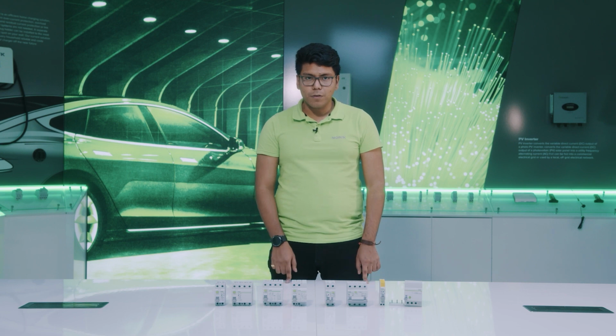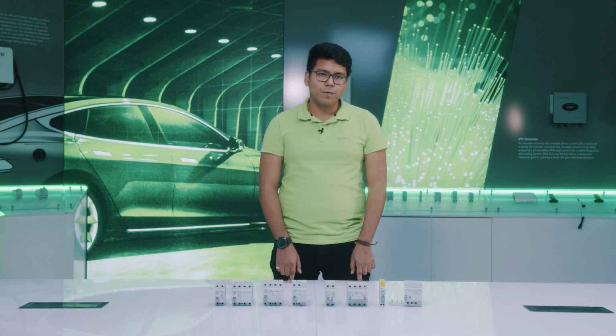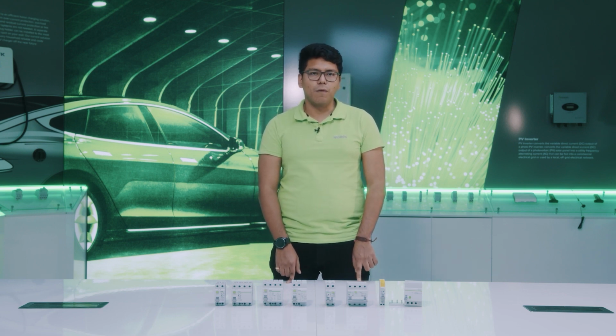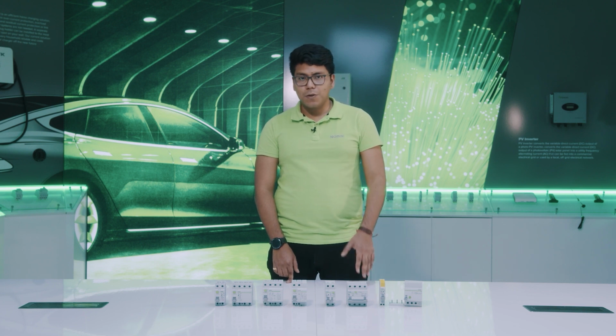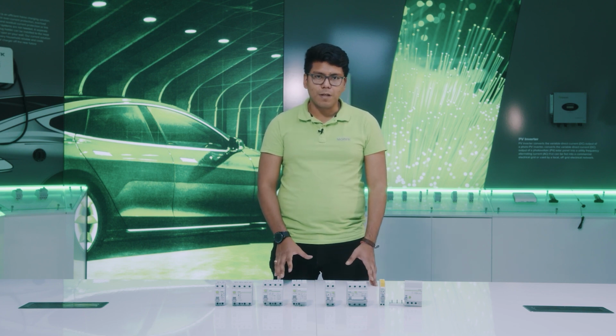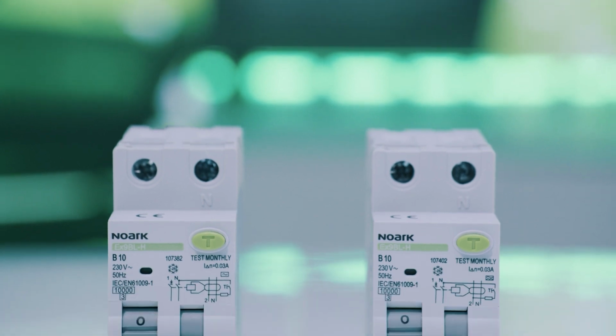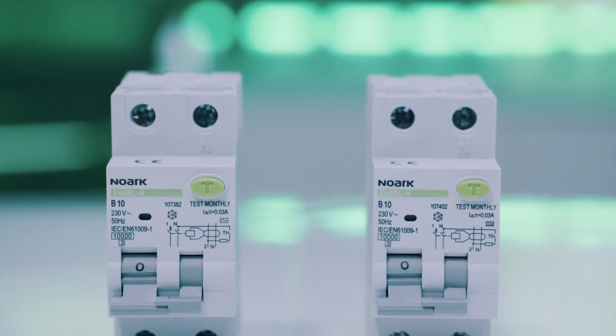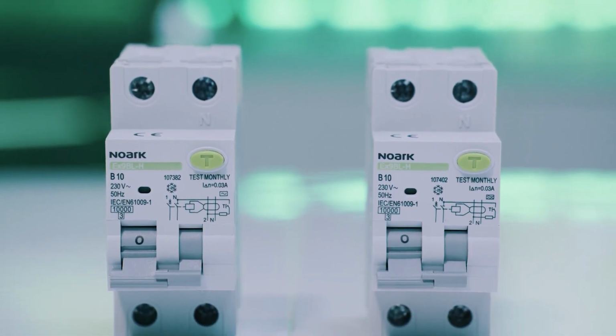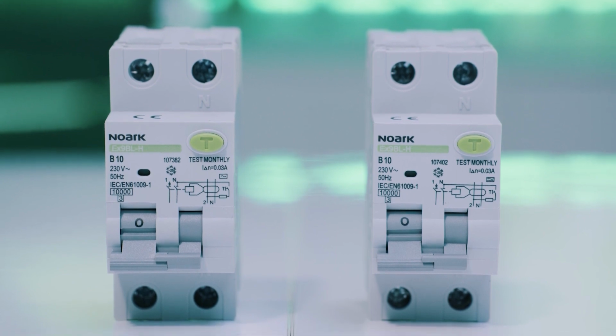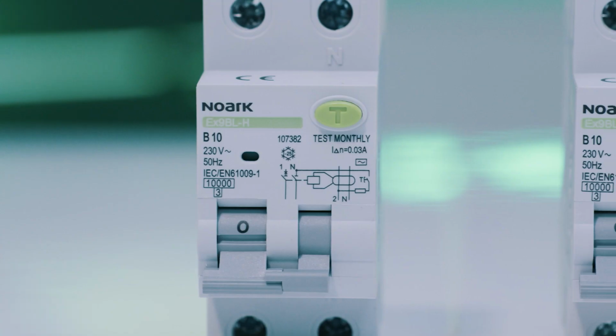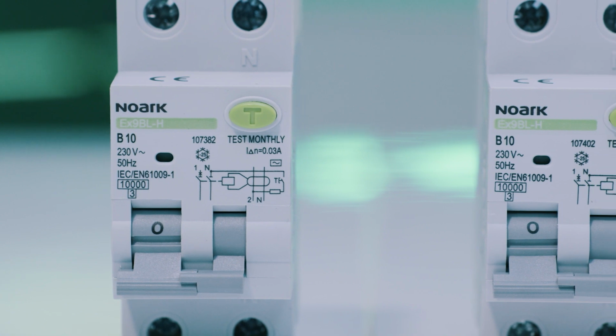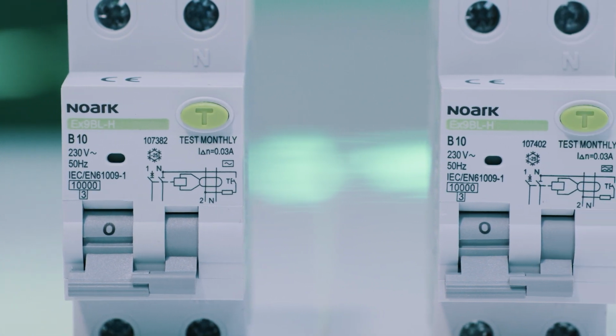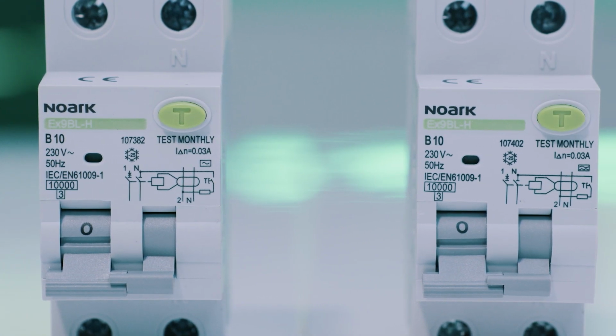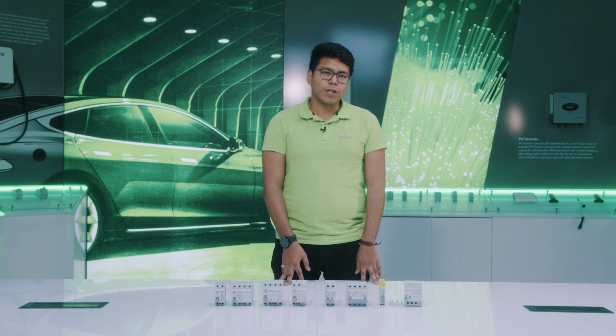In the Noark portfolio, you can also find RCBOs, known as residual current devices with overload protection. It's actually a combination of RCCB and MCB in one device. The EX9BL RCBO is provided with 6 kA or 10 kA breaking capacities, up to 40 amps in 2 pole version. You can find there AC or A type of RCCBs and B or C characteristics of the MCB part. Residual current sensitivities are 30, 100 and 300 milliamps.